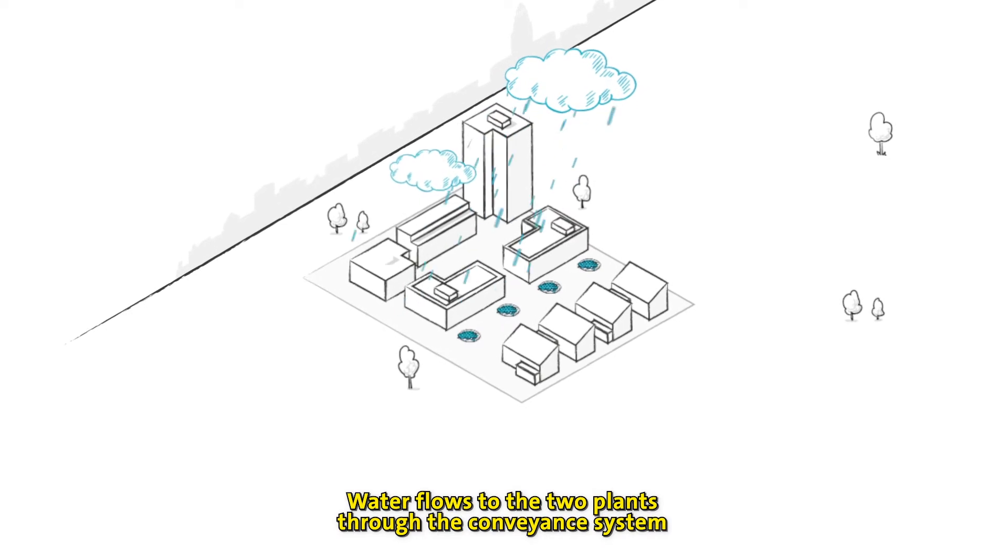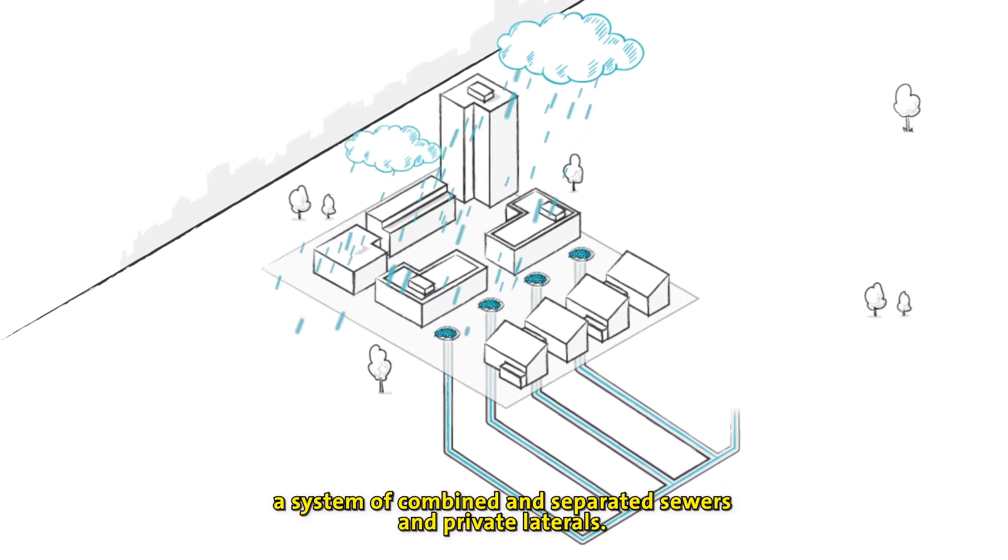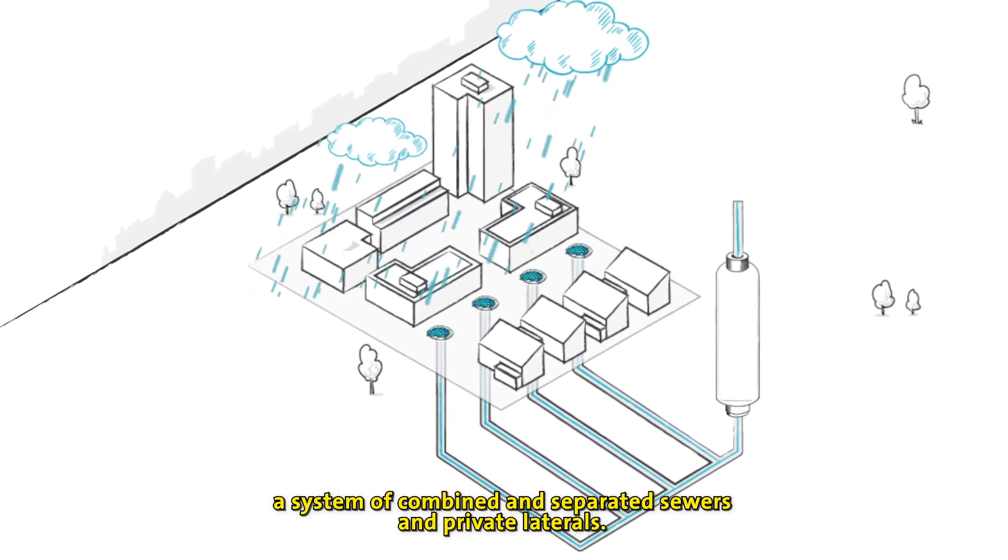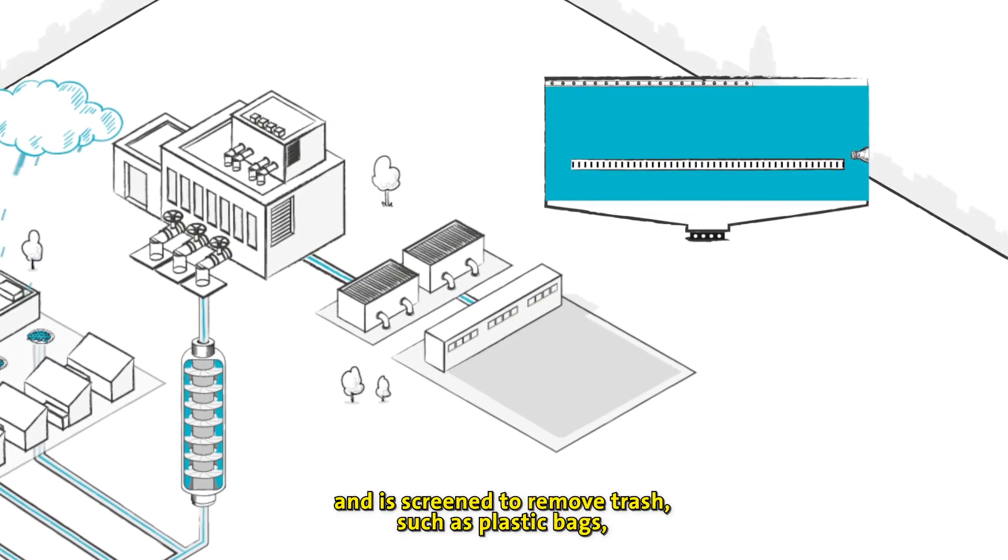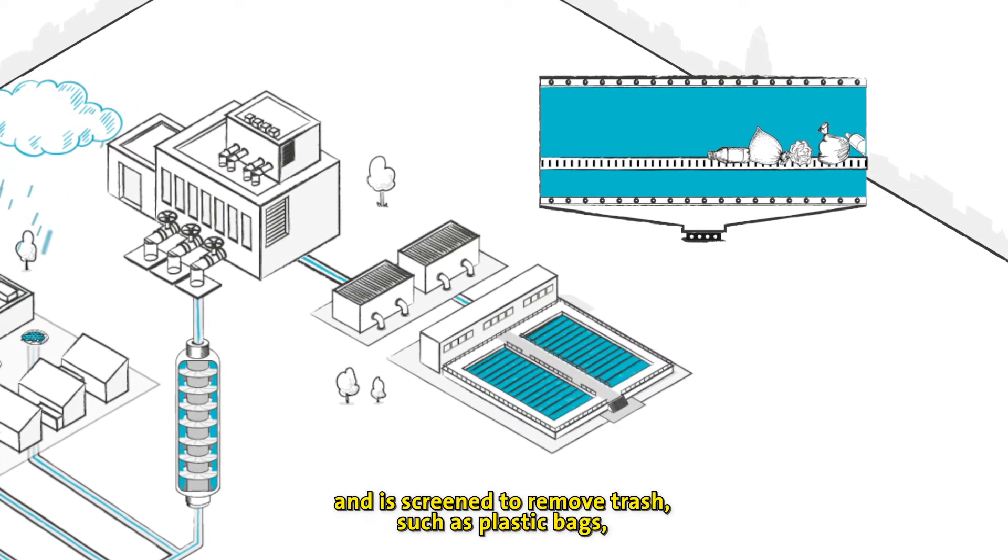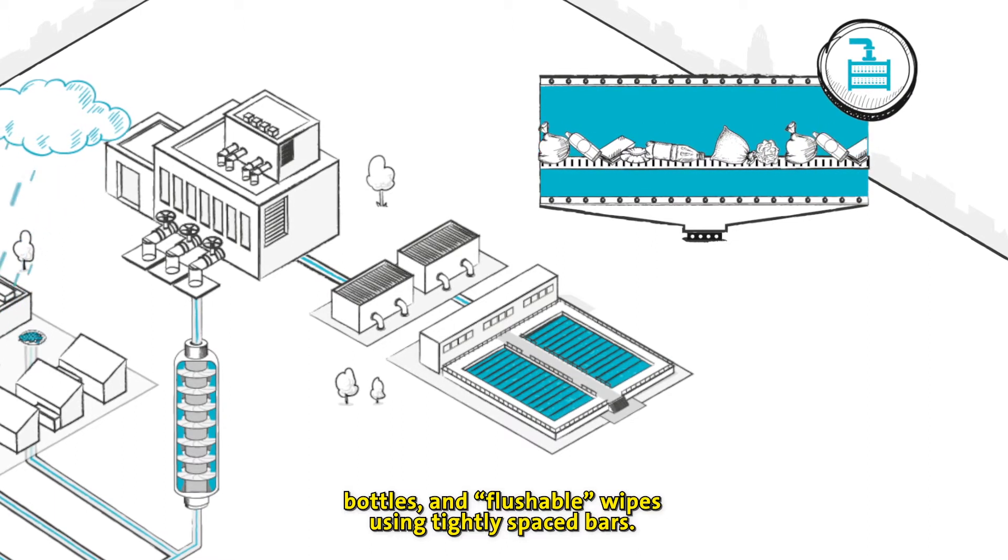Water flows to the two plants through the conveyance system, a system of combined and separated sewers and private laterals. Water is brought up from underground using Archimedes screws and is screened to remove trash, such as plastic bags, bottles and flushable wipes, using tightly spaced bars.